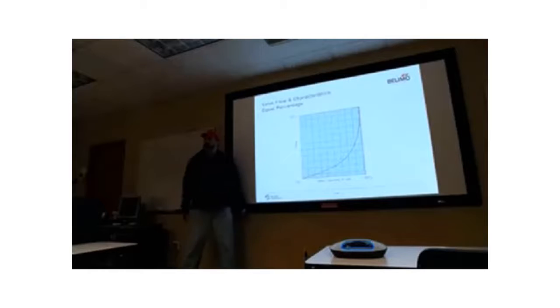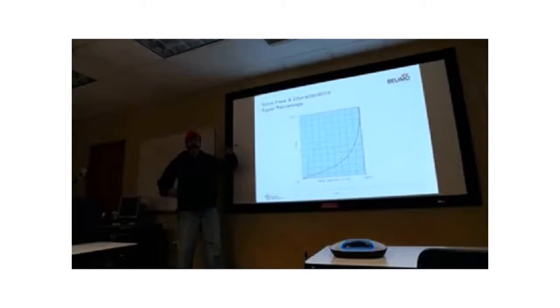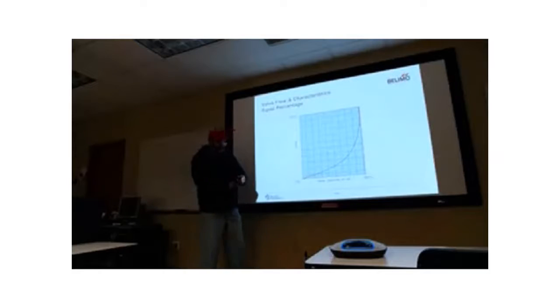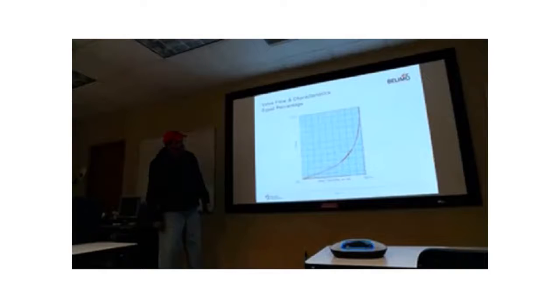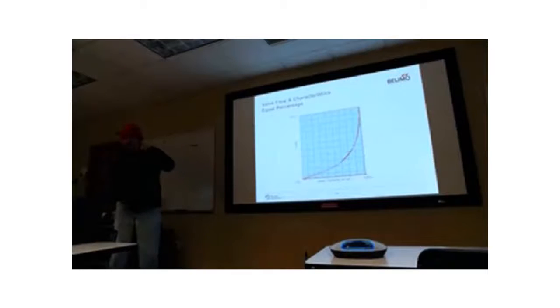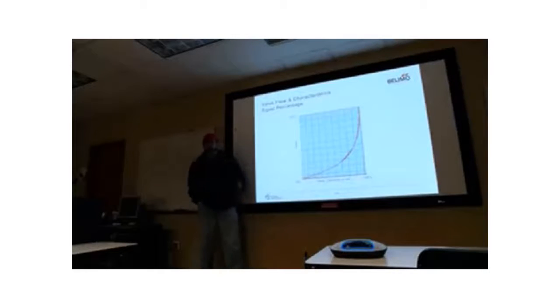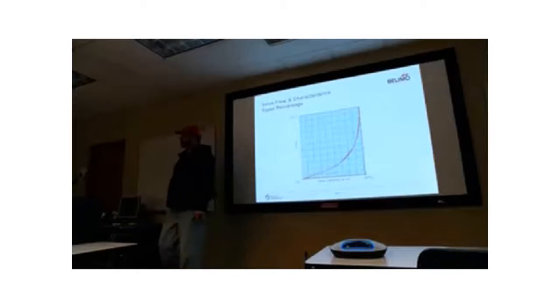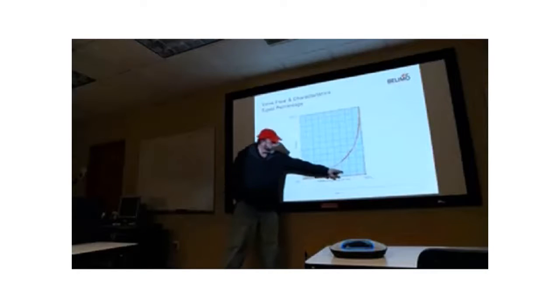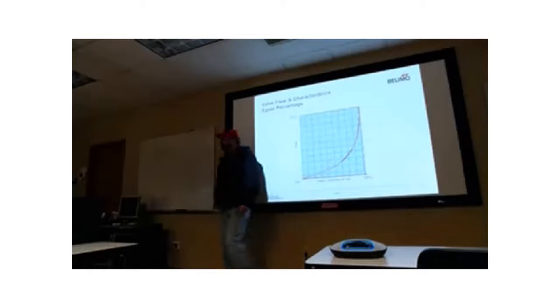Okay, this third one here is called equal percentage. Now, I don't care about the math. There's some math on this, but what I want to show you guys is this curve. So you look at it and you go, okay. And then I tell you, for almost all of your hydronic coils, like heating coils and cooling coils that you have out in your buildings, almost all of those valves, the control ports, are equal percentage. And you go, no way. You're telling me, John, that if I open my valve like 30% open, I'm only going to have like 8% of the flow through it? And even if I open it up to like 70%, I'm still only getting like 35% of the flow through it?